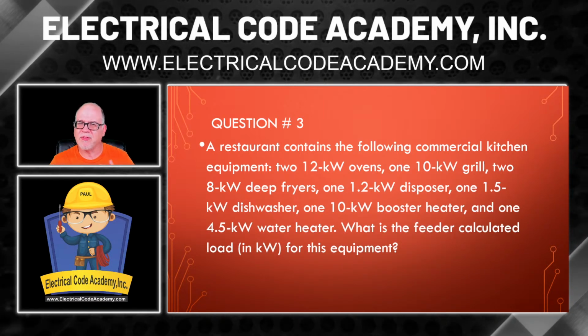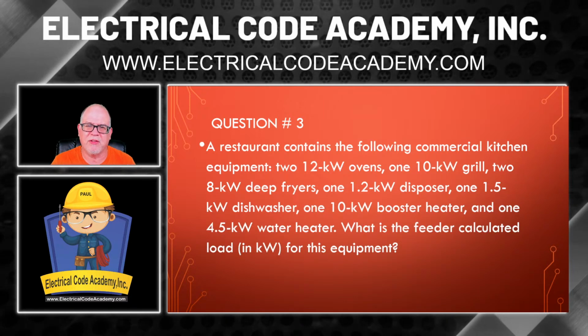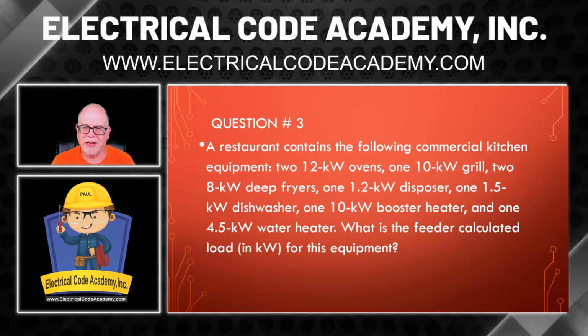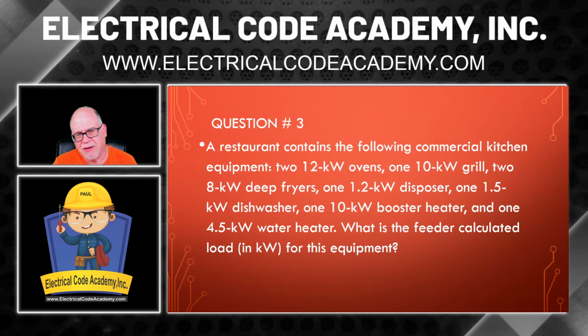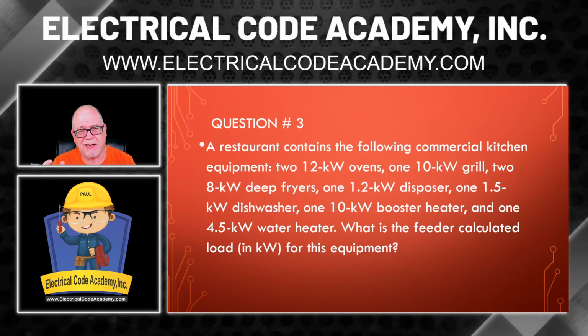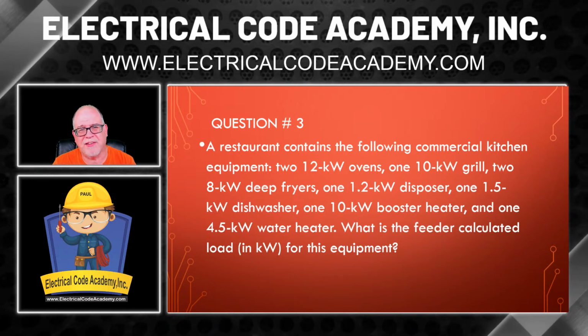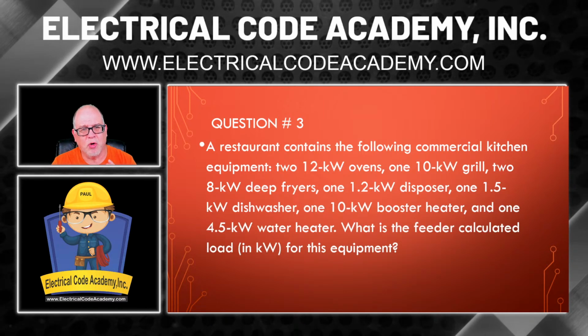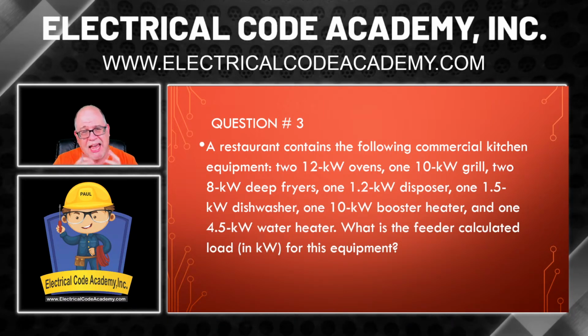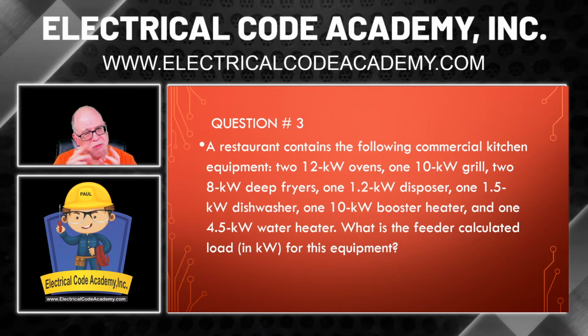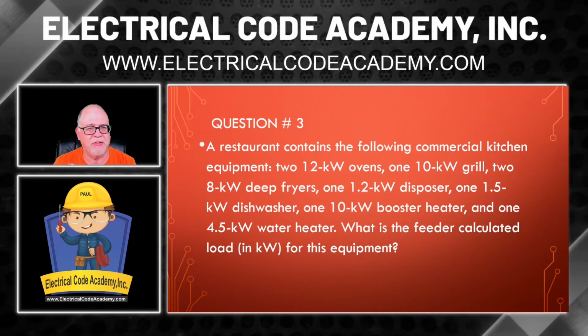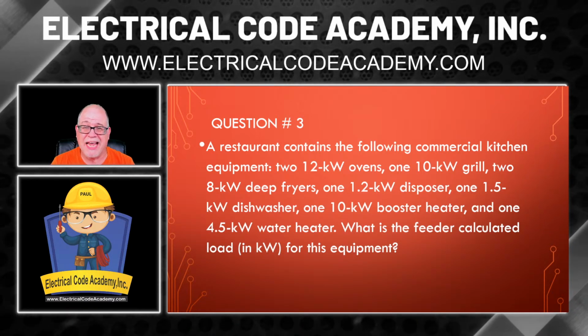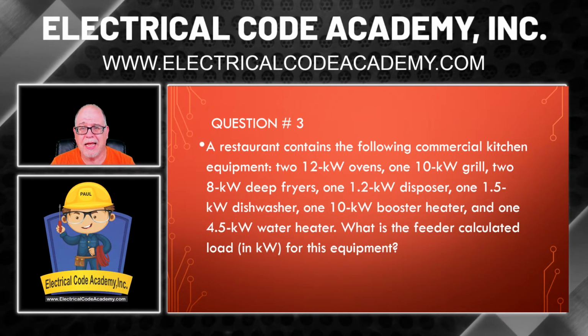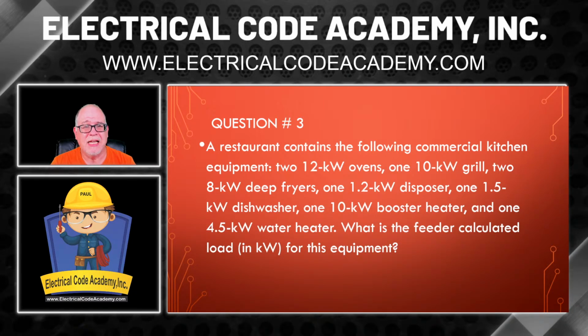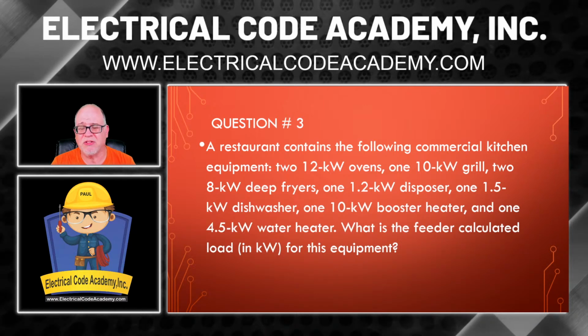Now, remember different terminologies, and we've covered this in other videos. You have what's called a connected load, and you have what's called a calculated load. A calculated load is very similar to when they say, what is the demand load? It means you're implying something's getting added to this, or some kind of demand is being applied. There's a calculation to take place. Whereas a connected load is simply adding everything up. And that's the first thing that I want to do. I want to go on and get my total connected load.